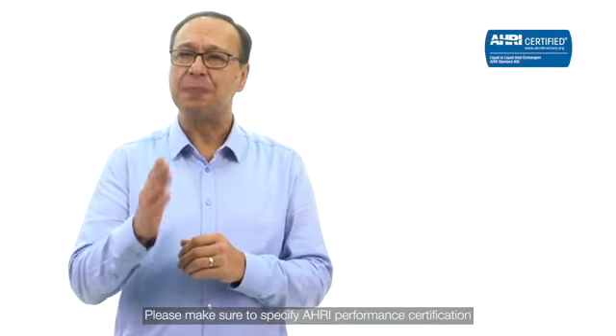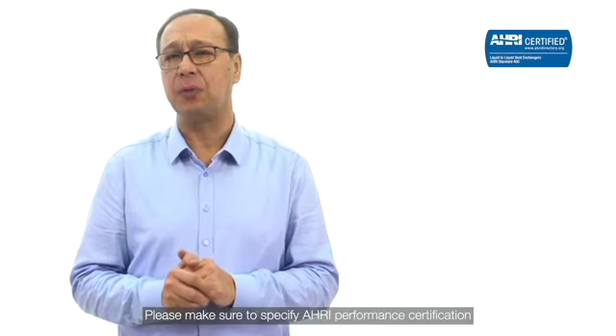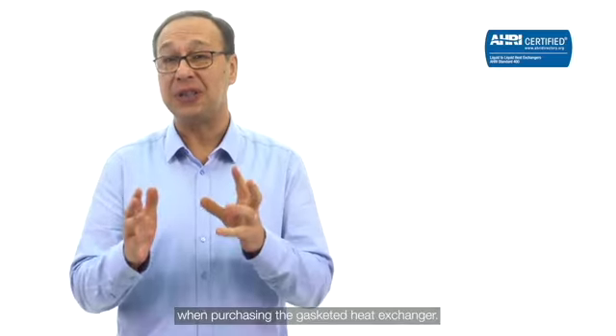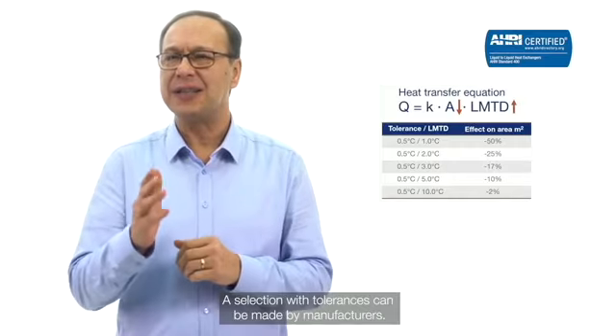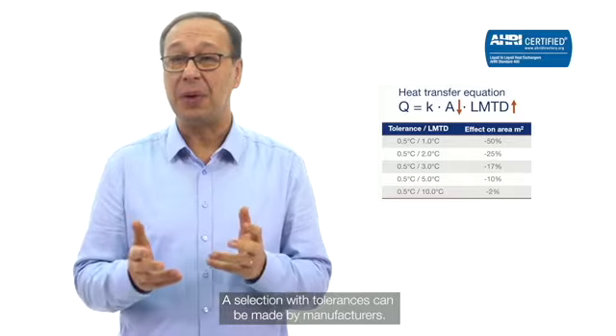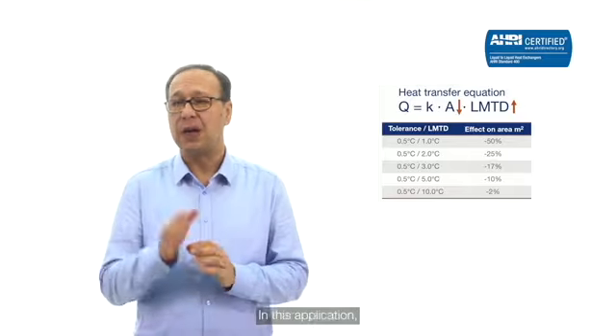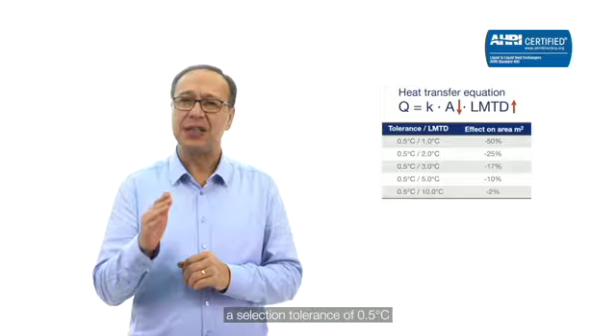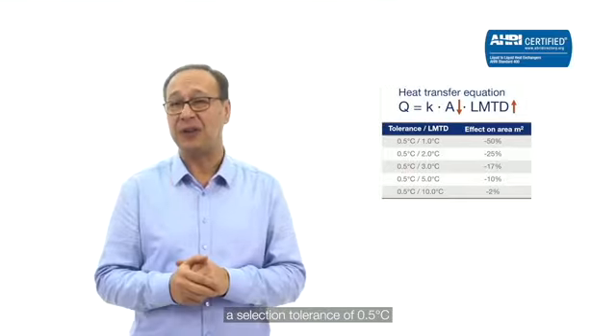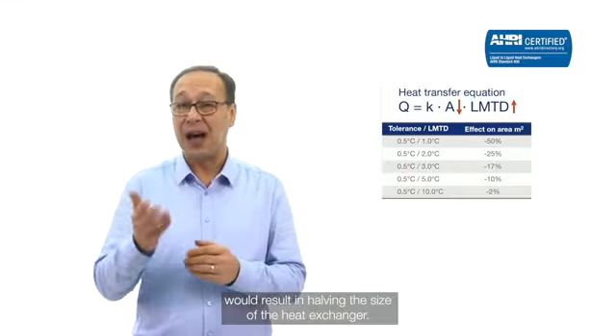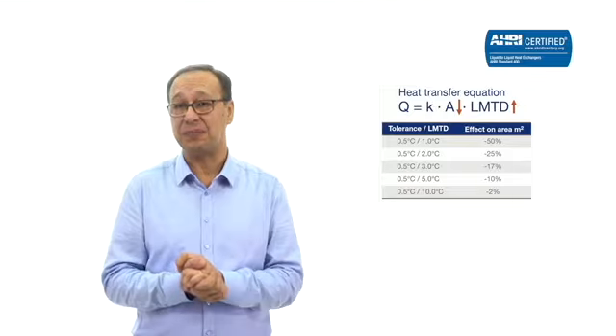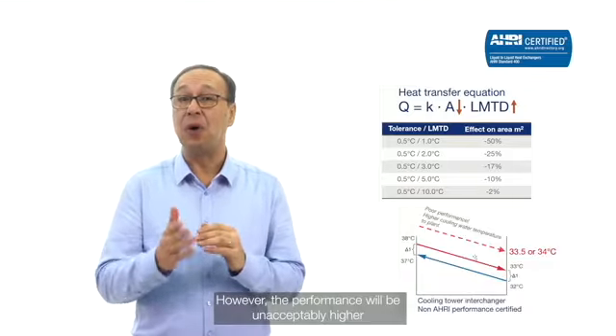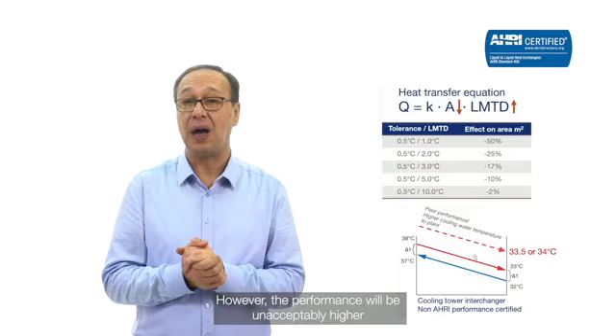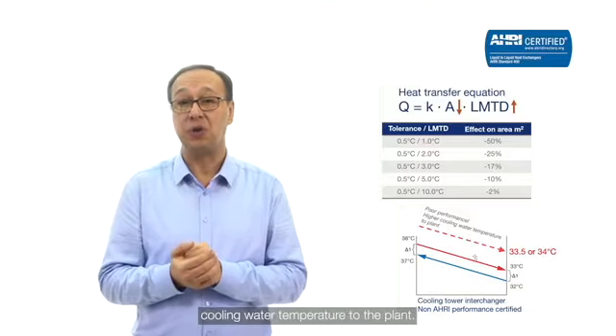Some words of caution. Please make sure to specify AHRI performance certification when purchasing the gasketed heat exchanger, as selection with tolerances can be made by manufacturers. In this application, a selection tolerance of 0.5 degree Celsius would result in halving the size of the heat exchanger. However, the performance will be unacceptably higher cooling water temperature to the plant.